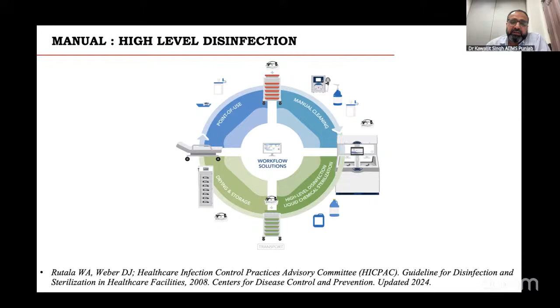I will quickly narrate this, and in the sequential slides, I have given a brief description of this. As we have already discussed, the first is pre-cleaning, which is very, very important. The previous speaker has already gone through it. I will just go with a few lines, followed by a leak testing. Leak test is very important for the flexible scopes, and the scopes which fail the leak test should directly move to the service, and they are not to be used.